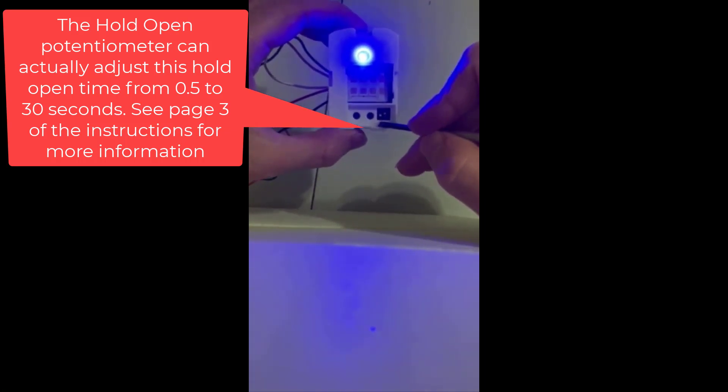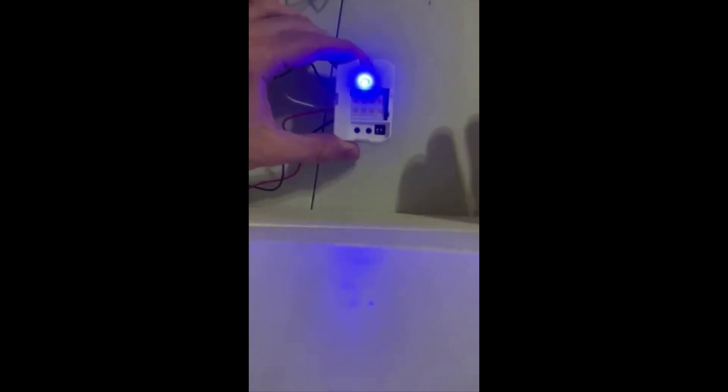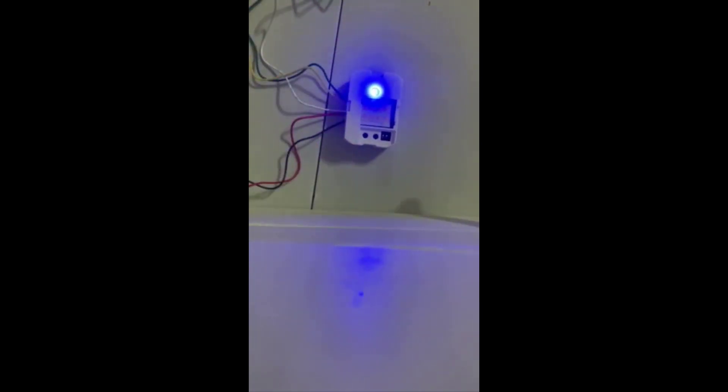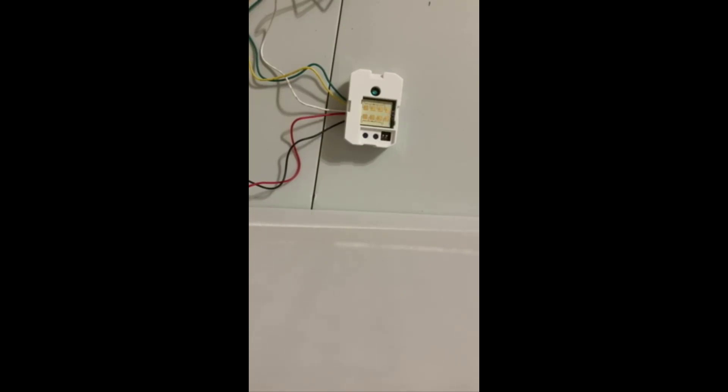If you have this dip switch changed though from the factory default of down and you have it set up, now that's going to make it behave differently because now we're in toggle mode. So toggle mode acts like a light switch. When you wave your hand in front of that sensor the first time, it's like flipping a light switch up and it's just going to constantly hold that signal to the operator which in turn will constantly hold that door open.